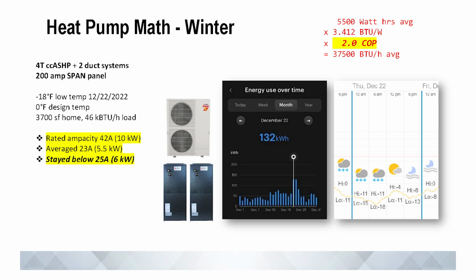What really stands out to me is that it did this at way below the rated energy use. The rated ampacity for this system is 42 amps. The average during this way-below-design condition was 23 amps — just a portion of rated capacity — and it never went above 25 amps.